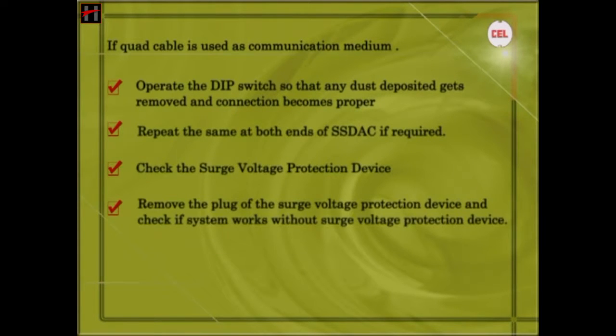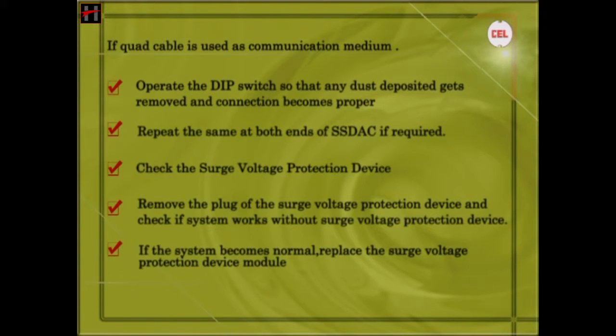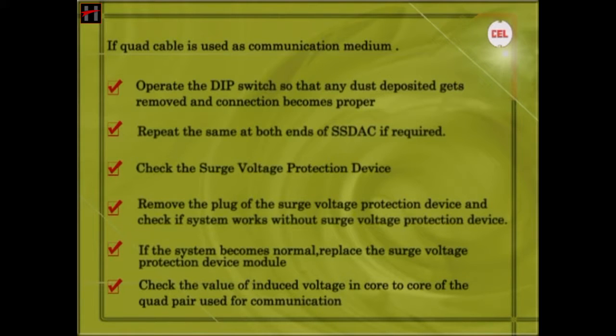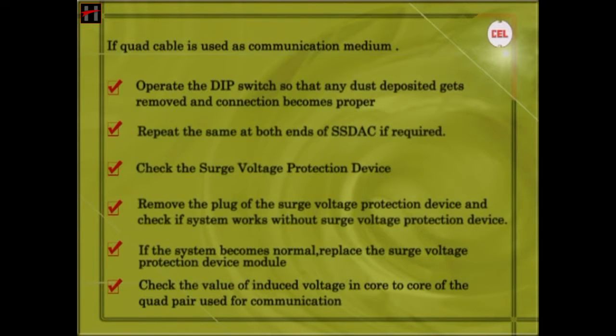Check the surge voltage protection device. Remove the plug of the surge voltage protection device and check if the system is working without it. If the system becomes normal, replace the surge voltage protection device module. Check the value of the induced voltage in core to core of the quad pair used for communication. If induction is more than 5 to 10 volts, change the pair.